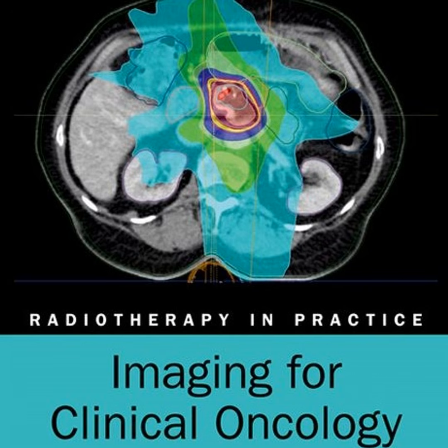Exactly, lots of noise. Iterative reconstruction tackles this by making an initial assumption about what the patient's internal anatomy looks like. It then simulates what the X-ray data should look like based on that assumption. Oh, I see. Then the computer compares its simulation to the actual messy data collected by the scanner, calculates the difference, and updates its assumption. And it just keeps doing that. Over and over, it repeats this cycle, these iterations, dozens or hundreds of times in a matter of seconds. Whoa. By constantly refining the mathematical model against the raw data, the algorithm actively strips away the noise. So you get a razor-sharp image of tissue density while exposing the patient to a fraction of the ionizing radiation.